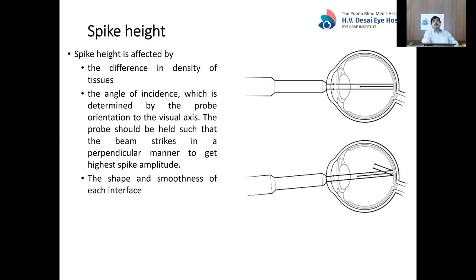Spike height is affected by the difference in densities between two tissues at the interface, but also by the angle of incidence, which is determined by probe orientation. Ideally, the probe should be aligned with the visual axis so the beam strikes perpendicular to the cornea, the anterior and posterior lens surfaces, and the retina, to get high spike amplitude. If not aligned, sound waves get deviated from the probe. The smoothness of the interface also matters — an irregular interface causes dispersion of sound waves.